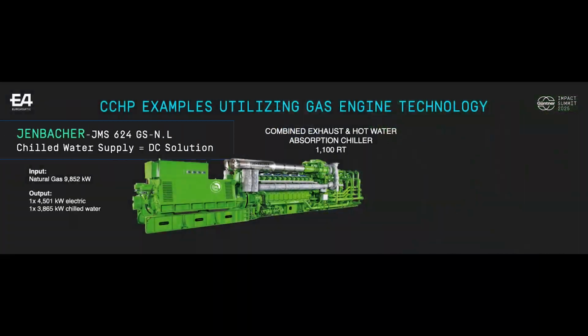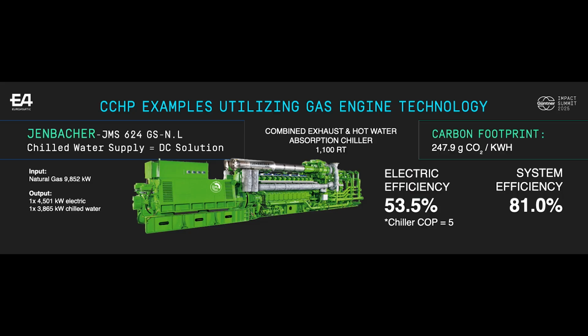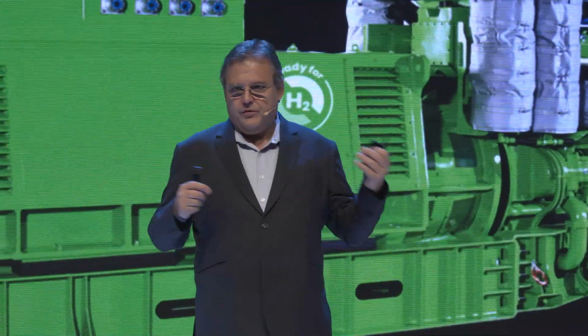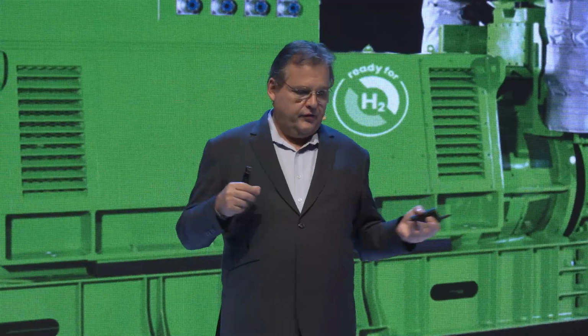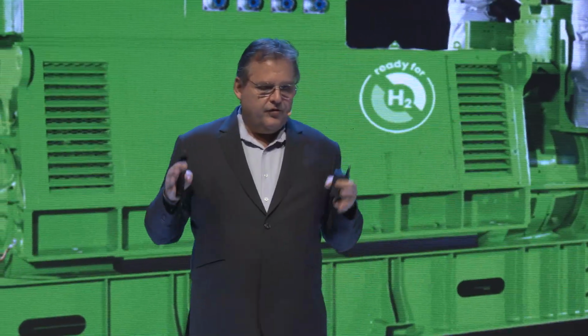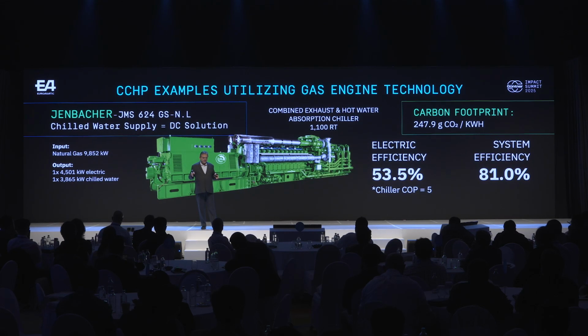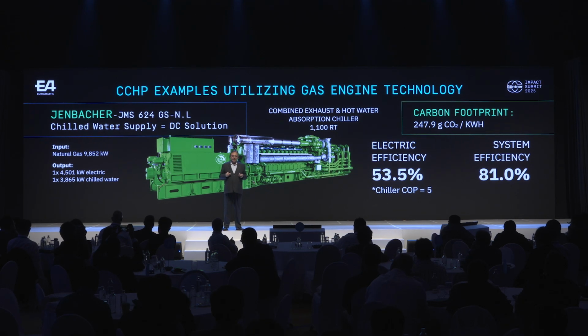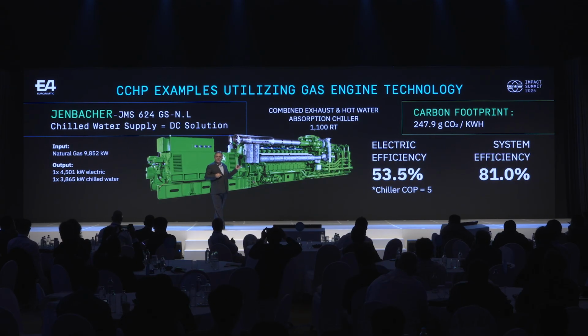And then we have everything into cooling. That's the one I want to talk a bit more about today, because we can reach here 81%. The cooling output you get from jacket water plus exhaust, or I prefer steam chillers, gives you 81% overall energy efficiency. With a chiller COP of 5, that would be about 53% electric efficiency when we calculate the electricity savings of the chiller. That puts you in a range better than a combined cycle power station.